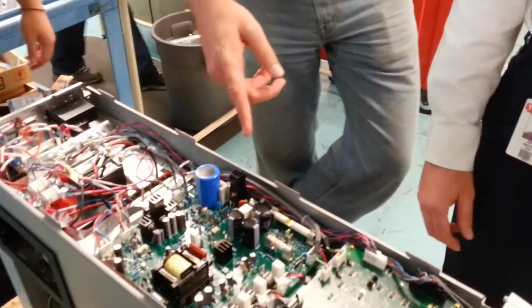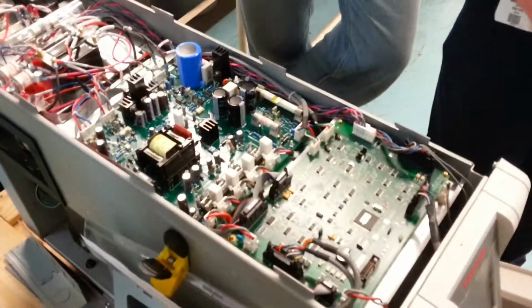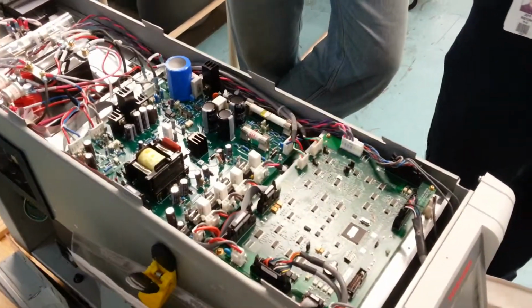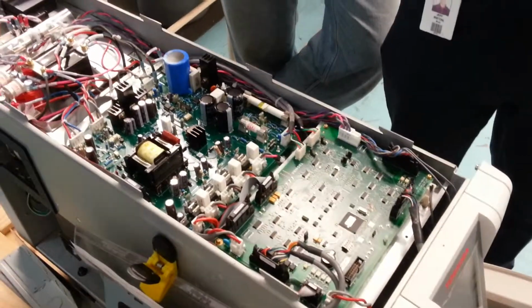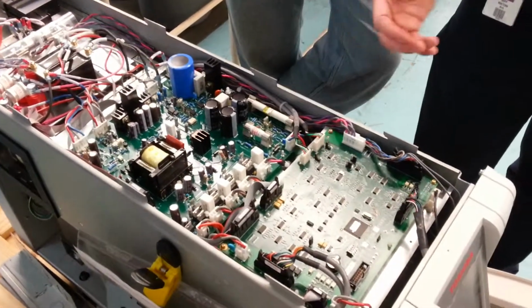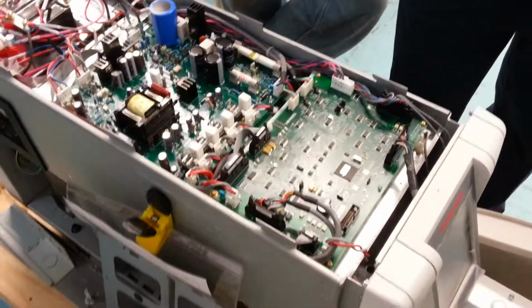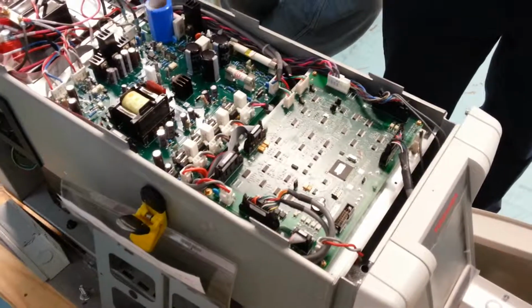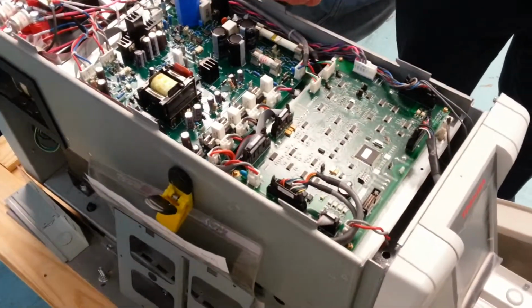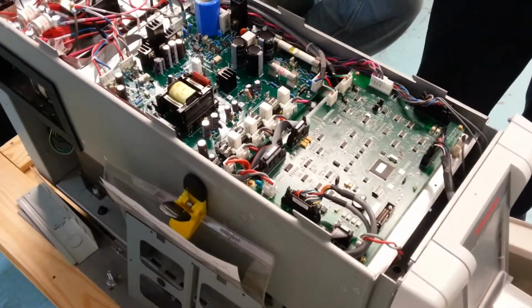How do you design the IGBT drive? The driver board itself is designed against whatever the IGBTs need as far as current, turn on, turn off, the actual rating of the current, the power supply for the positive, negative 15, and then a flyback transformer big enough to carry all that current.